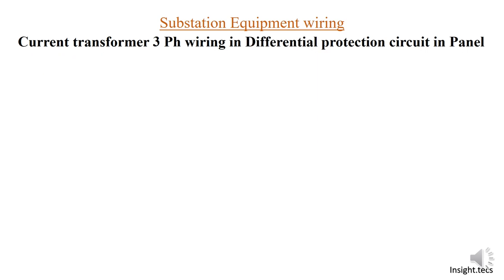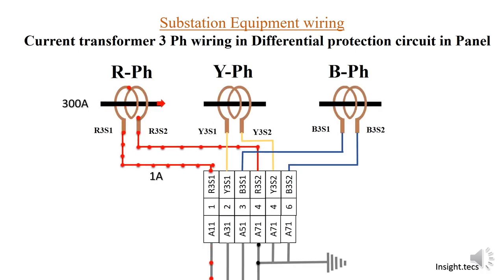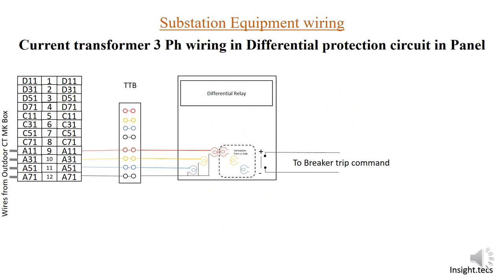Now let us move on to the differential protection wiring inside the panel. For differential protection, the core being used is r3s1, r3s2, and similarly for Y and B phases. The four wires coming out are a11, a31, a51, and a71. Once these four wires reach the panel, similar to the previous wiring, they pass through test terminal blocks and reach the differential relay. In the differential relay, there is also a connection from the LV side, where the current equivalent to the LV side is already flowing.